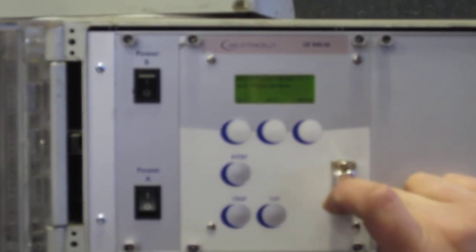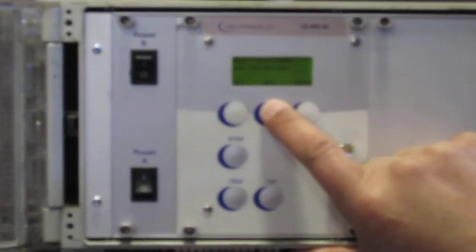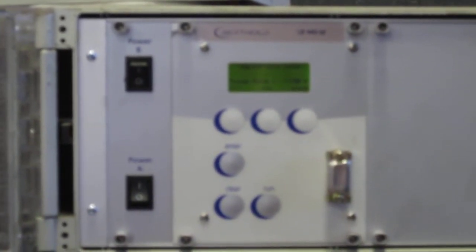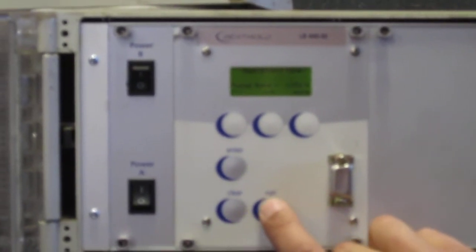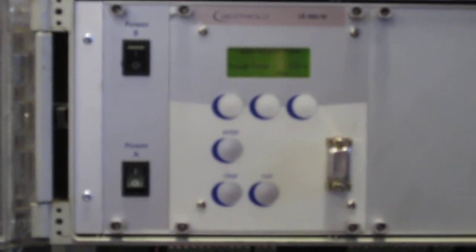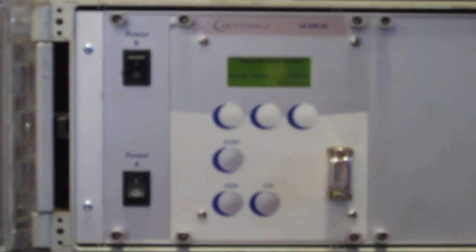So now we're going to go just straight to the calibration. In your case, right now we do have a rod detector. We picked that, so we want to do a background on the rod detector. So now we'll say run, and it's going to start reading in those count rates. Right now the vessel's empty, source is closed, and we have plates behind it to help block any stray radiation that's coming off the source. So now we have nothing but the atmosphere background.